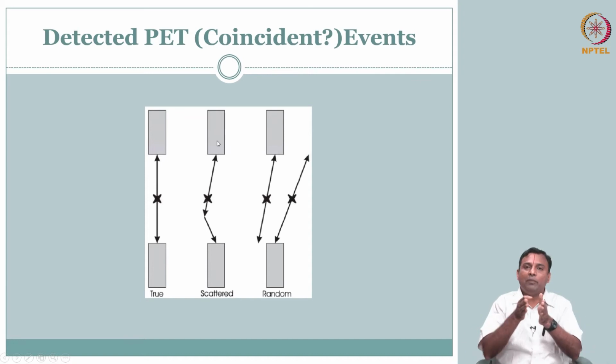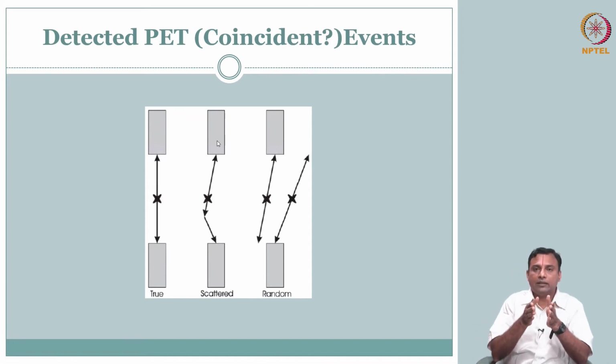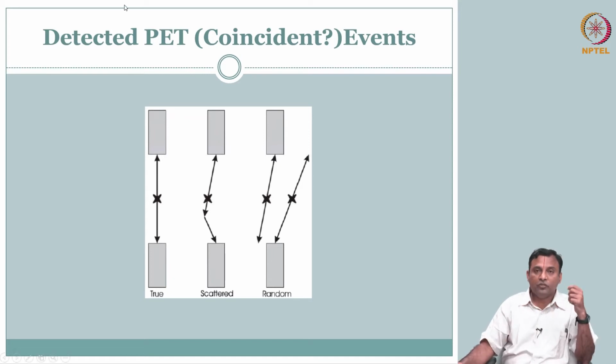How can we reduce that? Maybe we can go for a thinner crystal. But if you go for a thinner crystal, maybe it is not catching the gamma photon, right. So since we have the coincident circuit, that is a blessing, but how can we reduce this probability?